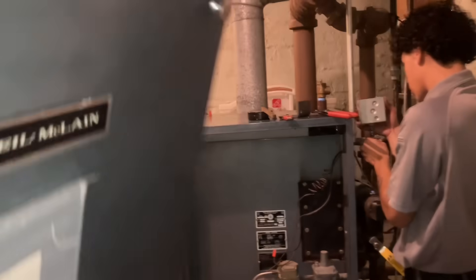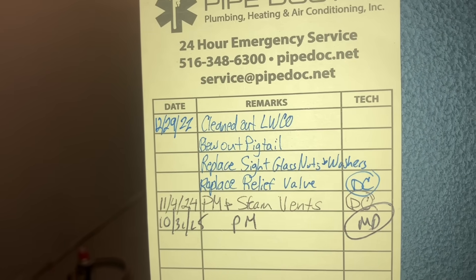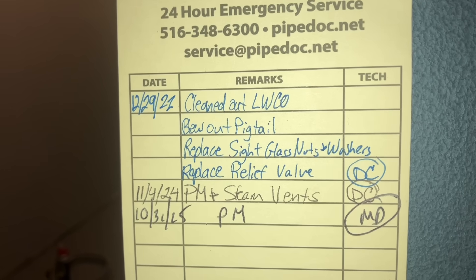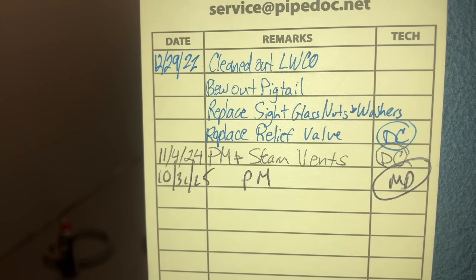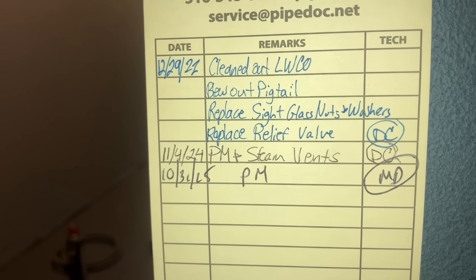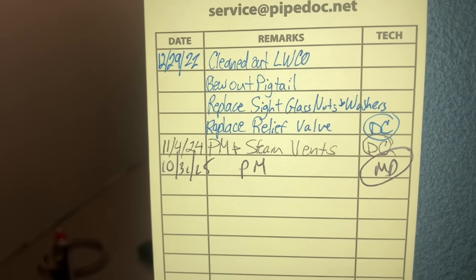And then many years later, Pipe Doctor's here. On 12-29 of 2022, we cleaned out the low-water cutoff, blew out the pigtail, replaced sight glass nuts and washers, and replaced the relief valve — Daniel did that. And then last November 4th, preventative maintenance and steam vents — Daniel was there as well. And then today, the 31st, Halloween 2025, MD and Derek for preventative maintenance. We're going to finish that combustion analysis, put the new printout there, and put a copy of that combustion analysis on the email receipt that we're going to give the homeowner.